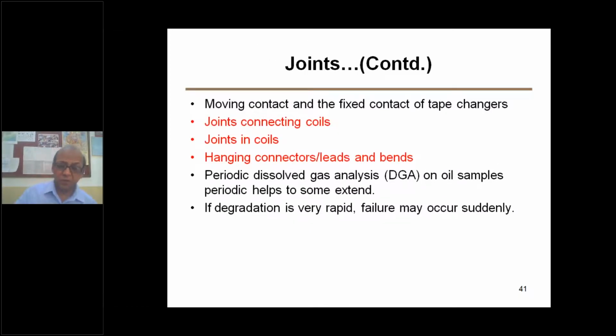So you must take care in the tap changers, that is one particular area of joints and moving parts, then joints connecting coils, and joints within the coils. Avoid joints within the coils. If at all you have to do it, then there must be proper joints. We are studying and coming out with our guidelines with practical data on how joints are to be made. Hanging conductors, yes, this is very important.